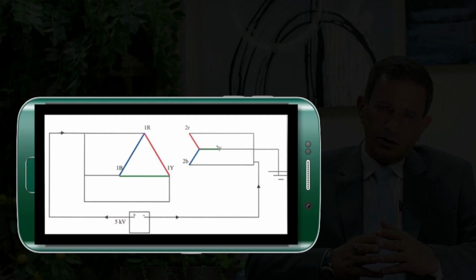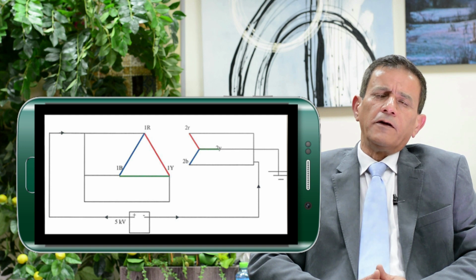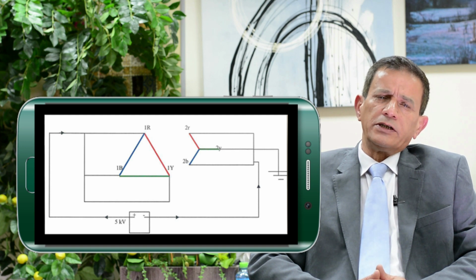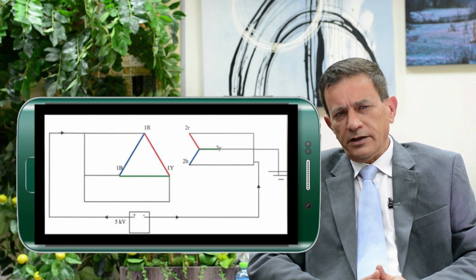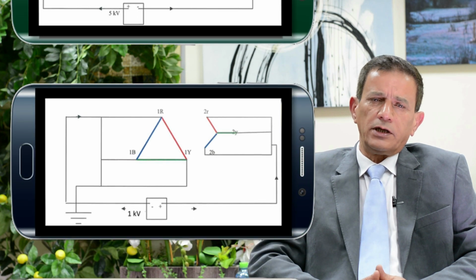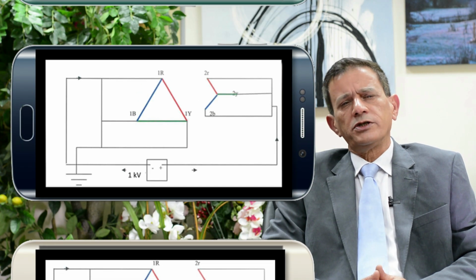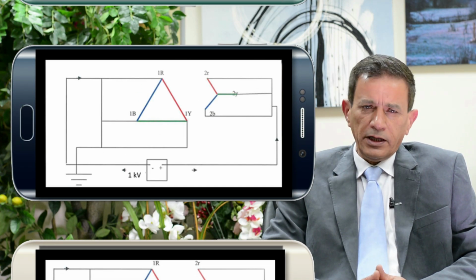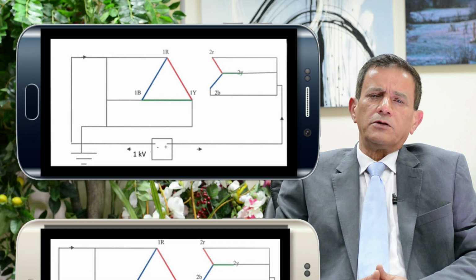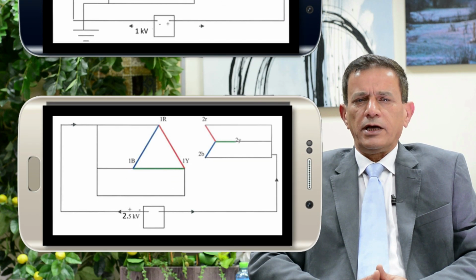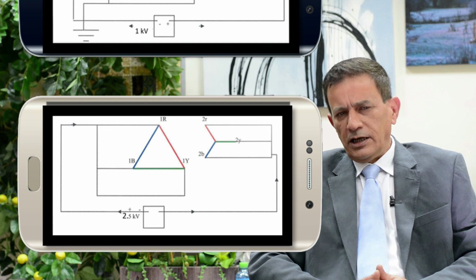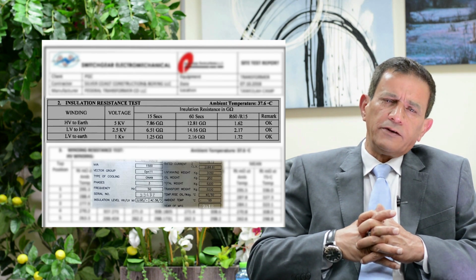high voltage side. This is the connection diagram for measuring the insulation resistance between the high voltage and the earth. And this one is the connection diagram for measuring the insulation resistance between the low voltage and the earth. And this one is for measuring the insulation resistance between the HV side and LV side. And here are the results obtained from this test.